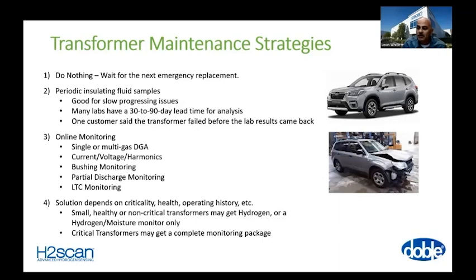For non-critical units, Tony, what do you guys see at the Doble Lab as far as typical oil sample times? It depends usually on the MVA of the transformer, and anything considered 10 MVA or above would usually be annual. Some places we went up to 50 MVA and higher, and they would be annual or two yearly. It depends on the individual organization, how risk averse they are, and how well they understand the oil sampling process. Right. We were talking to somebody at a conference recently who said at least their labs are currently looking at 30 to 90 day lead times to get analysis back.